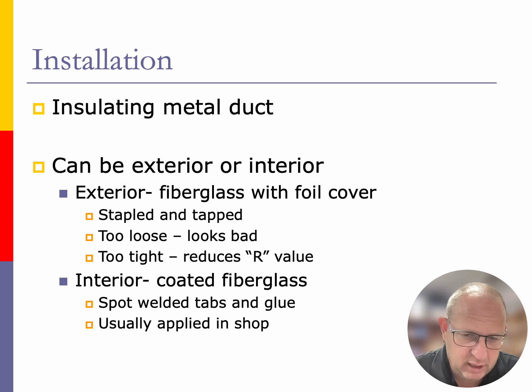That'd be the only reason that I would not prefer interior insulation on your ductwork, because over time this stuff is going to break down, and I don't like the idea that we have that type of insulation in the airstream that individuals are going to be breathing. So I prefer it on the exterior of the ductwork itself. Tabs will be glued to the inside of the ductwork, and before we bend up any type of ductwork, we'll lay a piece of insulation across it, and then we'll bend up the ductwork so that the insulation's nice and tight on the inside.